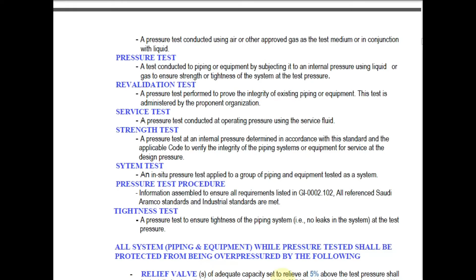All system piping and equipment while pressure tested shall be protected from being overpressured by the following. Relief valves of adequate capacity set to relieve at 5% above the test pressure shall be installed unless the test pressure is less than 85% SMYS, at which time it can be set at 10% above the test pressure. Sizing of these relief valves used for testing shall follow the requirements of API RP 520, Part 1. The relief valves shall be tested, dated, and tagged within 1 week prior to the pressure test for new construction projects, and within 1 month for maintenance operations.